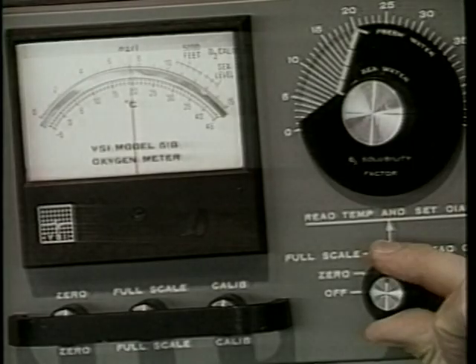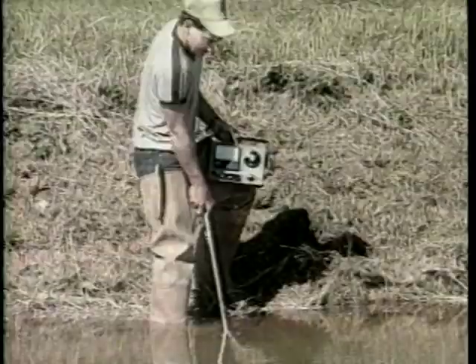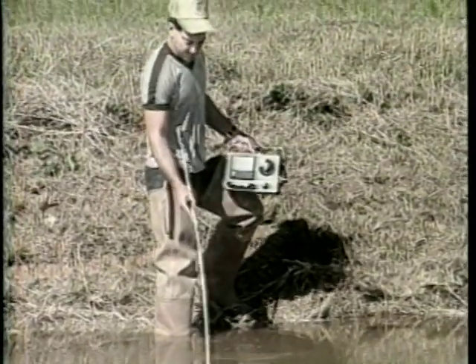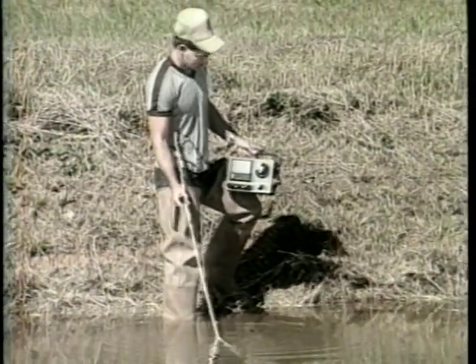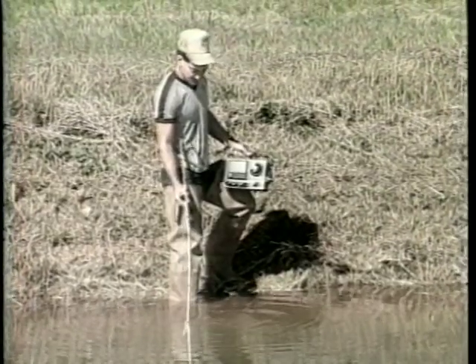The meter is then switched to the read O2 position and the probe is placed back into the water. The probe is then moved back and forth until a stable reading is obtained on the scale.